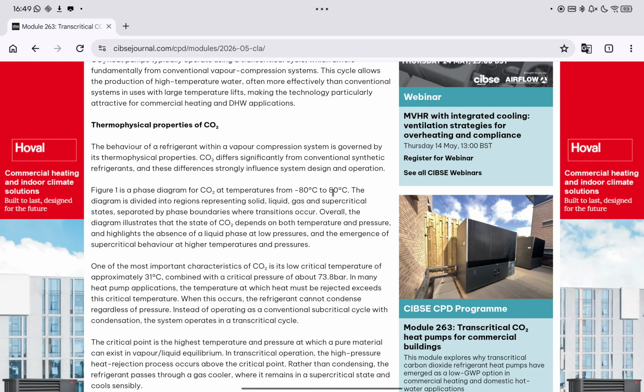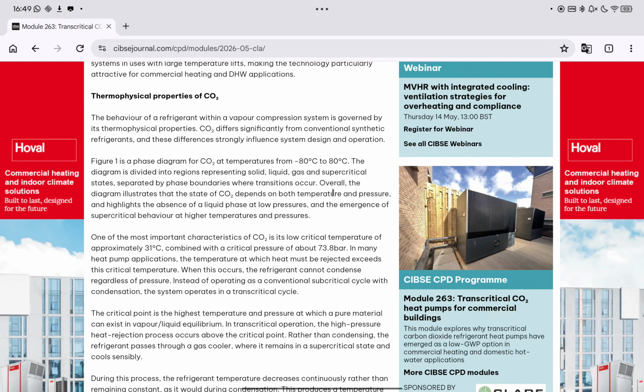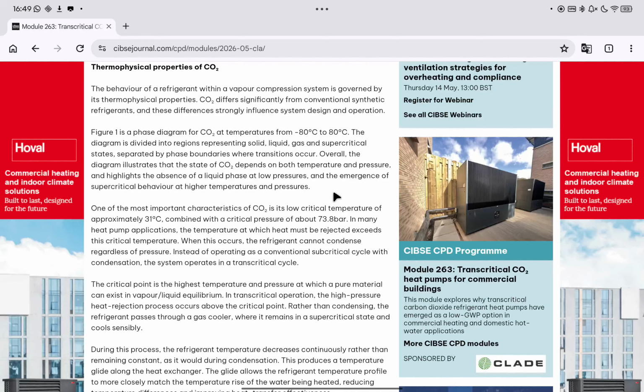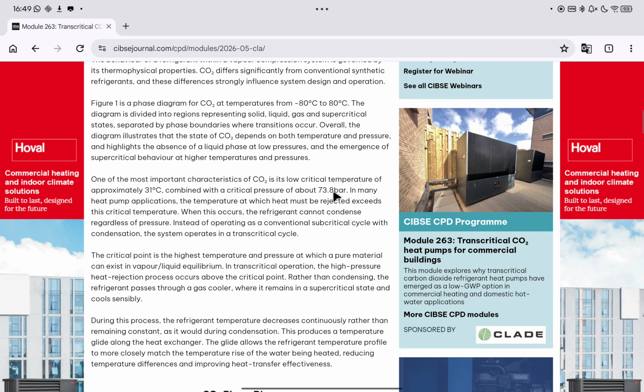In many heat pump applications, the temperature at which heat must be rejected exceeds this critical temperature. When this occurs, the refrigerant cannot condense regardless of pressure. Instead of operating as a conventional subcritical cycle with condensation, the system operates in a transcritical cycle. The critical point is the highest temperature and pressure at which a pure material can exist in vapor-liquid equilibrium. In transcritical operation, the high-pressure heat rejection process occurs above the critical point.